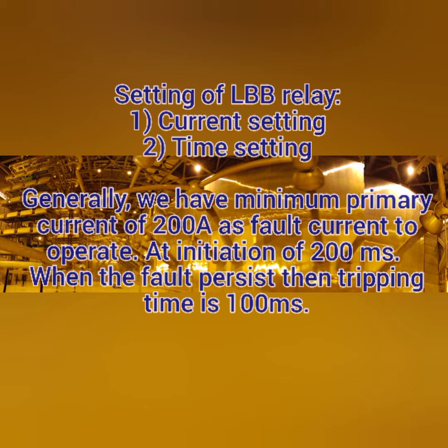Whenever the current is still persisting, which means the fault is persisting, the LBB relay will then give a tripping command to all the connected breakers of your bus. The tripping timing is as follows: first the initiation time of 200 milliseconds, as I said, and second your tripping time of 100 milliseconds. Within this 100 milliseconds the trip will be carried out.